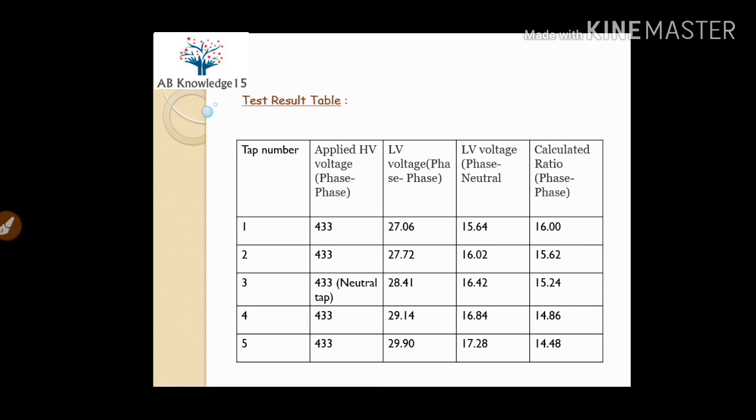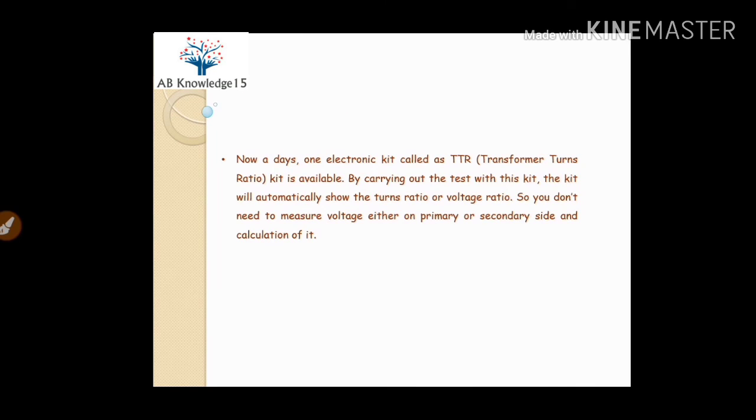Nowadays for carrying out the turns ratio test, one electronic kit is available called as TTR. Its full form is Transformer Turns Ratio kit. By carrying out the test with this kit, the kit will automatically show the turns ratio or voltage ratio, so you don't need to measure voltage either on primary or secondary side and calculation of it.